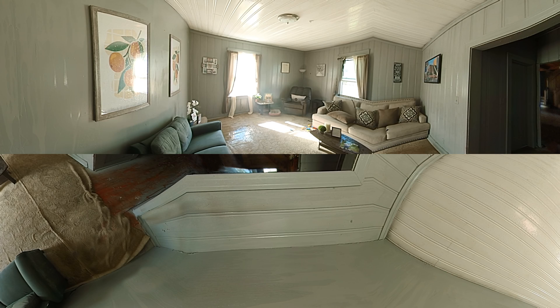Only the heat from fire activates the sprinkler, not smoke. In a typical house fire, only one sprinkler will activate. Take a close look at the room after the sprinkler activated. There is very little damage. The room is wet, but intact. Look around the room. If a family were sleeping, the sprinkler would have given them time to safely escape. The fire is confined to the room of origin, and the family would likely be able to stay in or move back into the home in a few days.